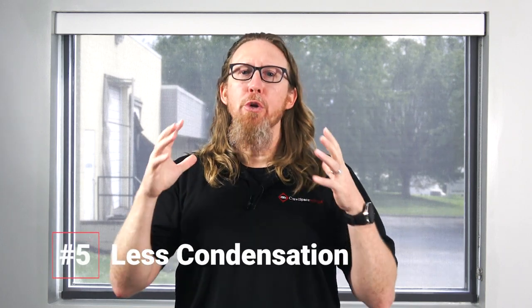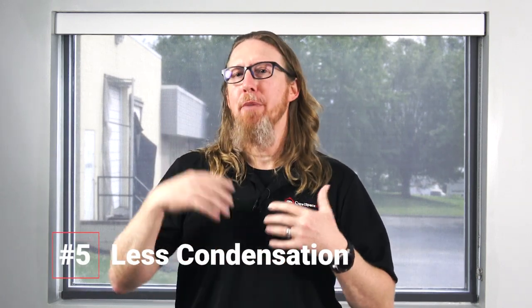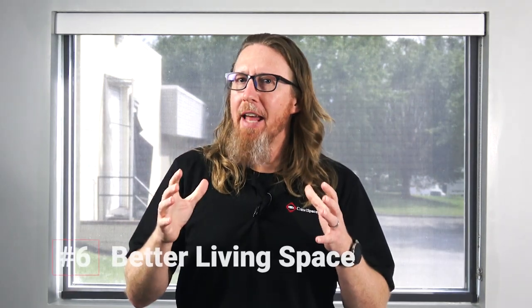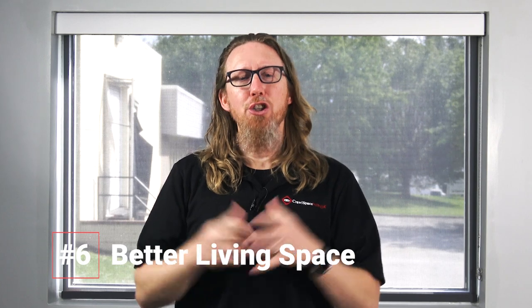Having a cooler attic is also going to reduce the risk of condensation in the attic. When you have really cold air ducts going through a super hot room, it increases condensation, and increased condensation increases the chances for mold. You don't want to create a moldy attic by having a hot attic. Cooling that attic down also reduces the risk of condensation in the living space - if you've got a cool ceiling and just above it a really hot surface like a hot attic, where those two meet can create condensation. Plus, if that ductwork is condensating, it could be dripping water onto your ceiling and creating a moisture problem inside the living space, which again can create a mold problem and an indoor air quality problem.